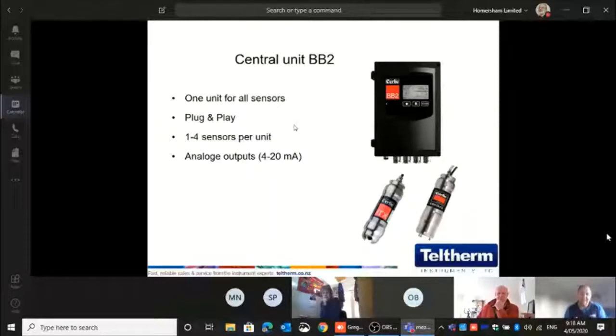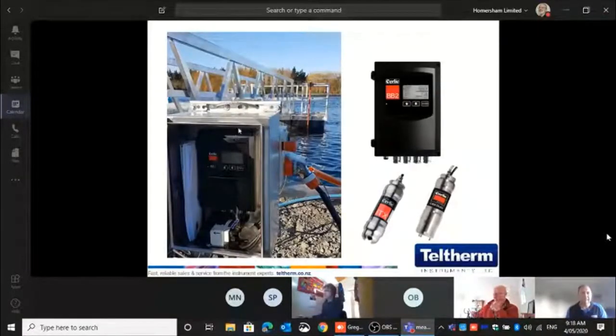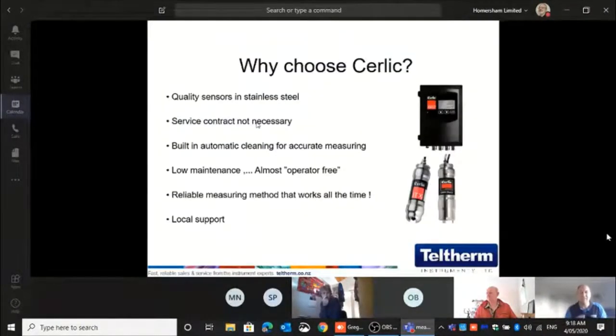So mainly if we do the commissioning and we come on site, that is where we sit, and that's what I show you. The controller, we don't really touch the sensors anymore. Don't really have to. Here you see that's, I think, Oxford at the Waimakariri District Council. Here you see the controller with the valve. So we supply the valve normally as well. But like I said, if you want to do that yourself, it's just a valve to transport the water, basically. That's all it is. Or air. I think they use air.